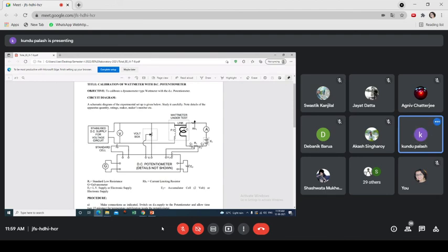Otherwise, for the current coil, there is no need, because the voltage drop across the standard resistance is within 1 volt. Why? For the maximum value of the current, that is at the rated value of the current coil, 5 ampere, and the resistance value is 0.1, so it will be 0.5 volt only. And 0.5 volt is a safe limit within the 2 volt that is applied across the V2 terminal. So there is no need to use the volt box in the current coil circuit. Only the volt box should be used in the potential coil circuit. Okay, understood sir.